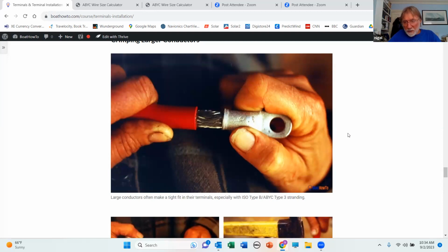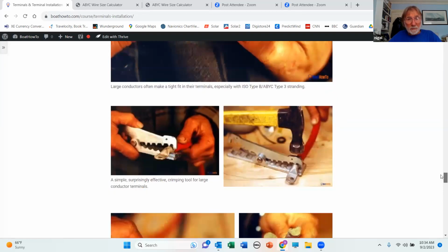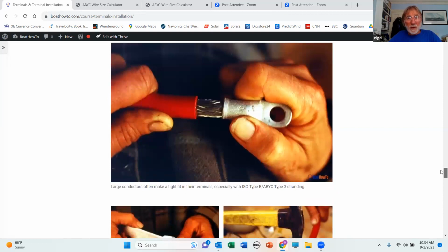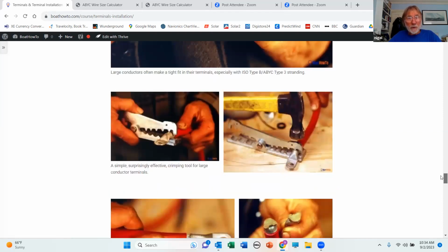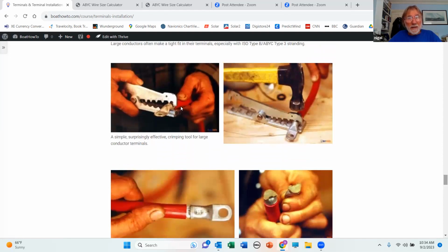So no, the bottom line is you need to find the right size terminals for the conductor. And I know it's very tempting. I've done it myself to mismatch things because you don't happen to have the right one on hand. But we need to try and resist that. When we get to those large terminals, they won't fit in that crimping tool. And there are some cheap tools on the market like this one. It has different slots for different size terminals, and it's spring loaded. You put the terminal in there, the spring holds that cap down, and then you beat on it with a hammer until this bit touches this bit. And it'll make a surprisingly good contact. There are other similar devices that you hit with a hammer to put these terminals on.